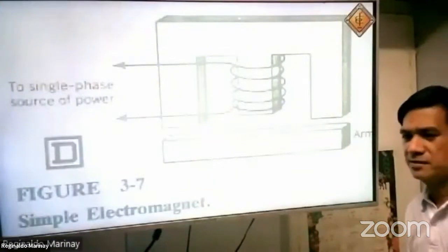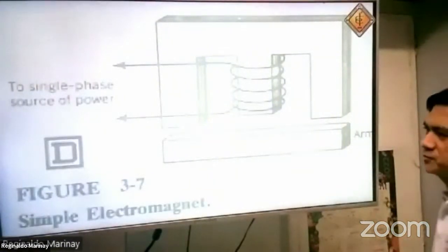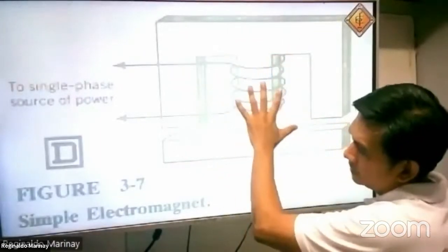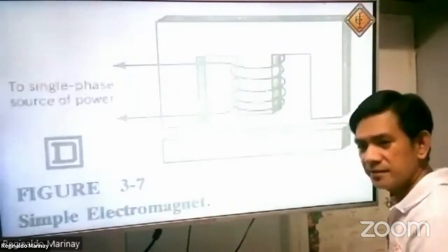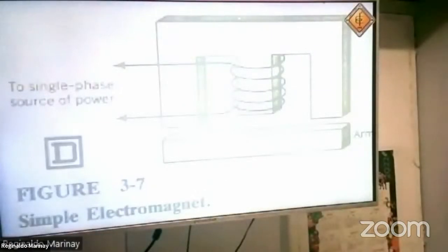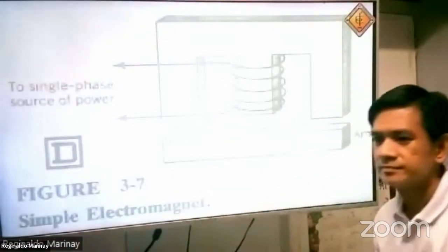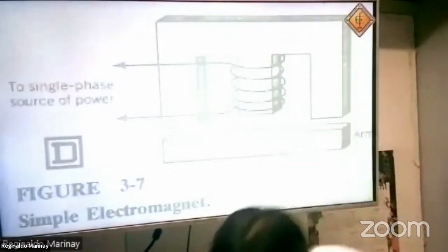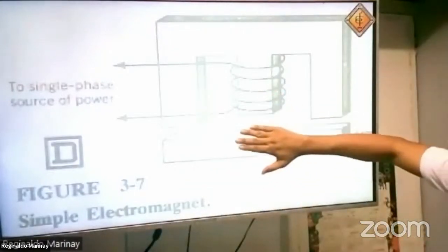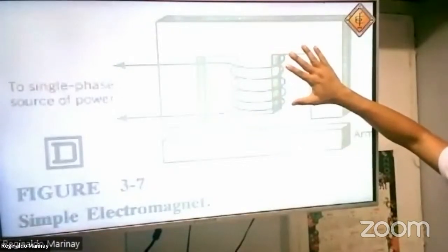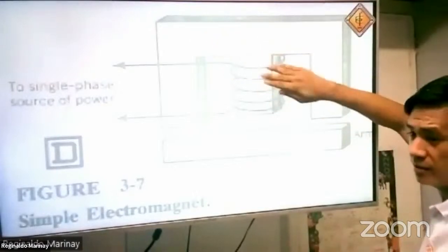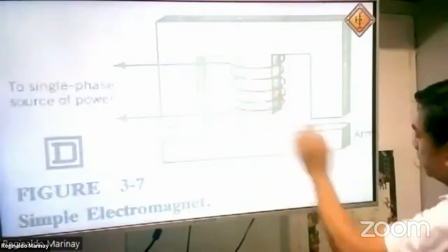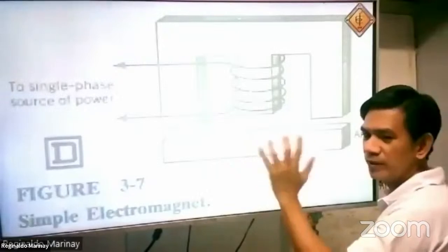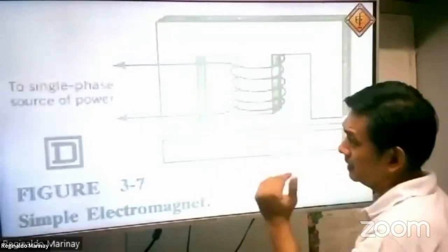What is the basic operation of a relay or a magnetic contactor? This is the most basic operation. You will see here, this is an electromagnet. This is a simple electromagnet. Can they see that, partner? So you will see here that this is an electromagnet. This represents an iron core, and this is the winding or the coil. So this is an iron core, this is the winding, and this movable element of the relay is what we call the armature. Armature, the moving part of the relay, is the armature.